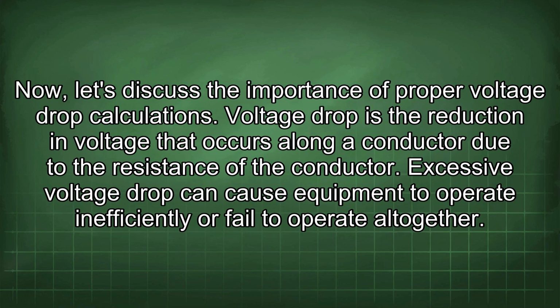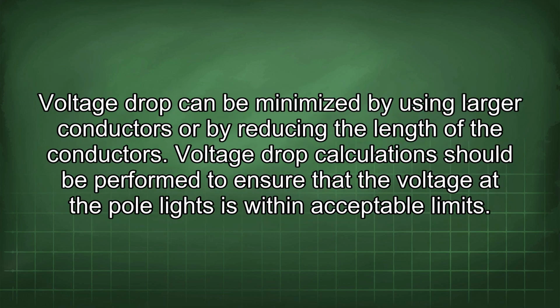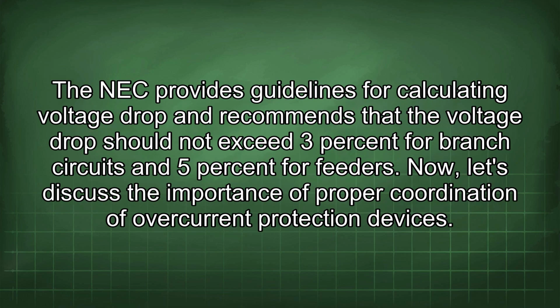Now let's discuss the importance of proper voltage drop calculations. Voltage drop is a reduction in voltage that occurs along a conductor due to the resistance of the conductor. Excessive voltage drop can cause equipment to operate inefficiently or fail to operate altogether. Voltage drop can be minimized by using larger conductors or by reducing the length of the conductors. Voltage drop calculation should be performed to ensure that the voltage at the pole lights is within acceptable limits. The NEC provides guidelines for calculating voltage drop and recommends that the voltage drop should not exceed 3% for branch circuits and 5% for feeders.